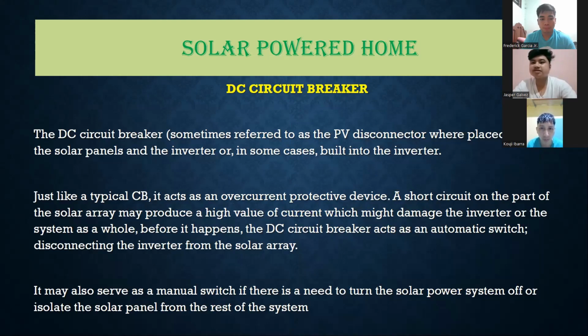DC circuit breaker. The DC circuit breaker, sometimes referred to as the PV disconnector, is placed between the solar panels and the inverter, or in some cases built into the inverter. Just like a typical circuit breaker, it acts as an overcurrent protective device. A short circuit on the part of the solar array may produce a high value of current which might damage the inverter or the system as a whole. Before it happens, the DC circuit breaker acts as an automatic switch, disconnecting the inverter from the solar array. It may also serve as a manual switch if there is a need to turn the solar power system off or isolate the solar panel from the rest of the system.